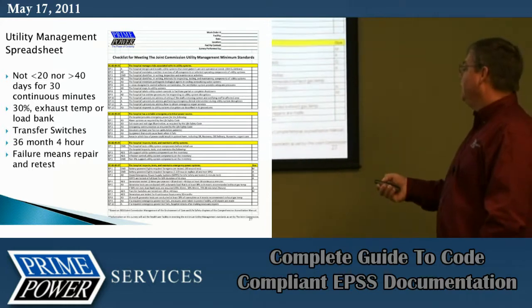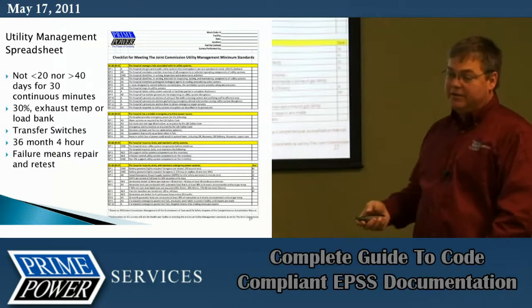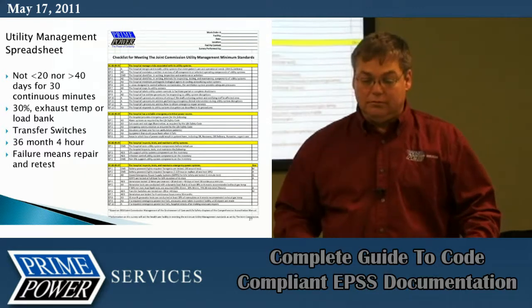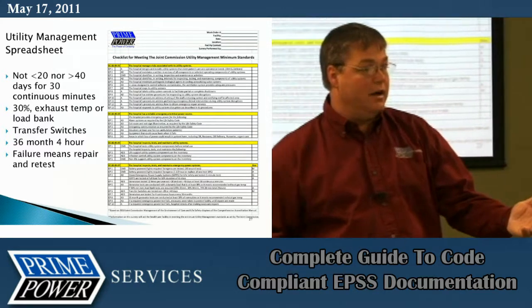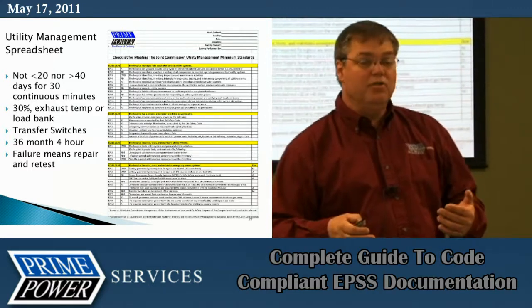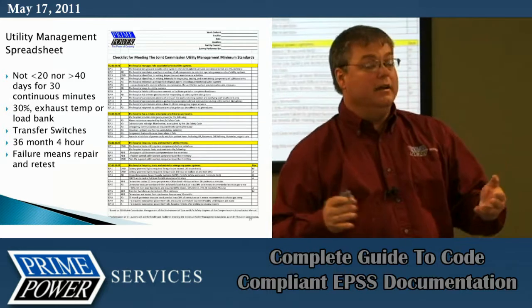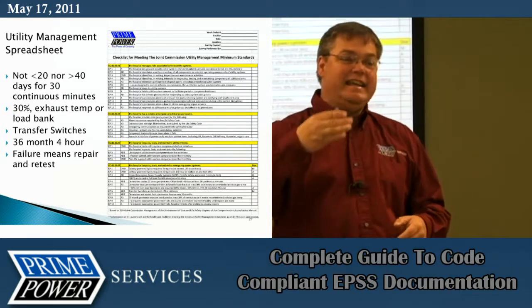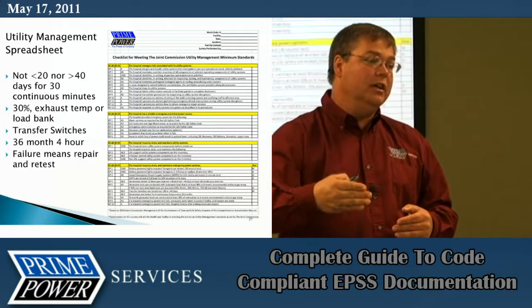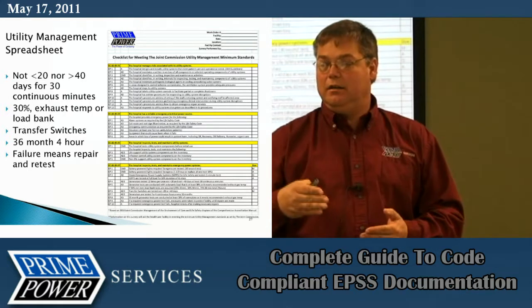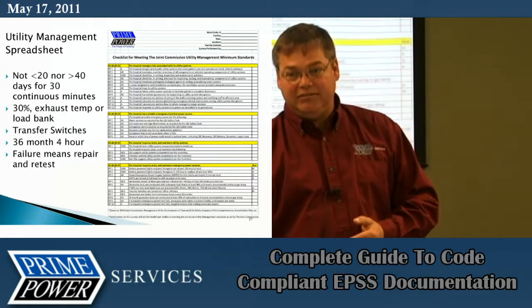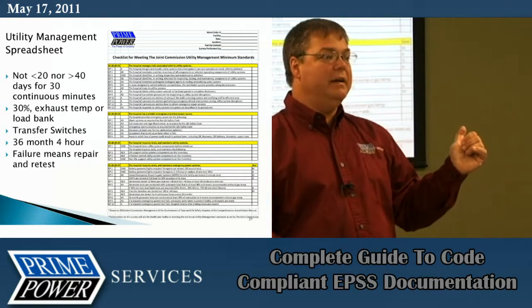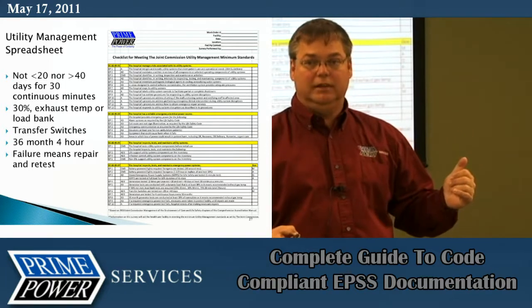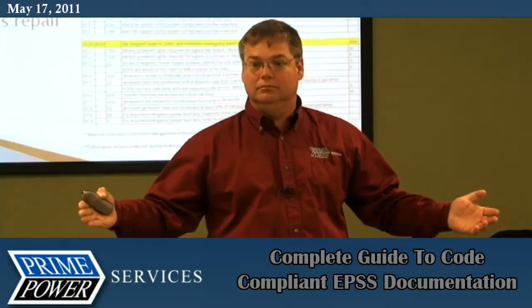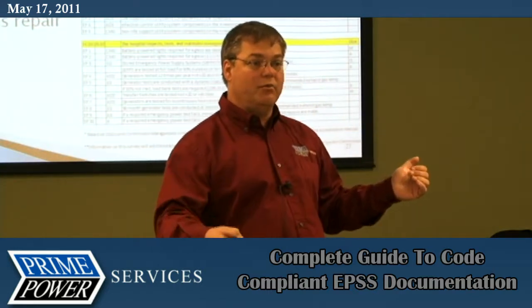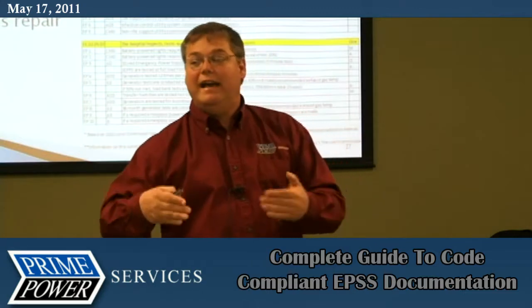If a required power test fails, does the hospital retest after making necessary repairs? I say this for everybody, healthcare or not: if your system has failed, you've repaired it, put in a new battery, called prime power, whatever the case may be, it needs to be checked out before you turn it back loose. Because when you say it's ready, you're depending on the inhabitants of that building to have their life safety protected by that generator firing. If the power goes off in a five-story building, they've got to get out. If that generator doesn't fire, you're messing with the components of the emergency preparedness system. So therefore, you have to test it.